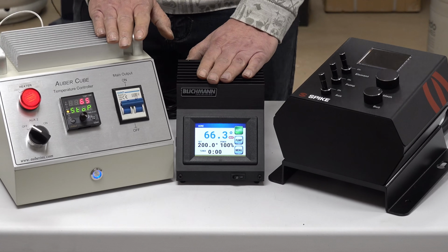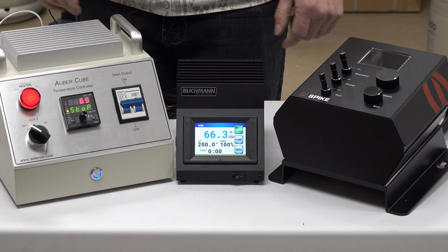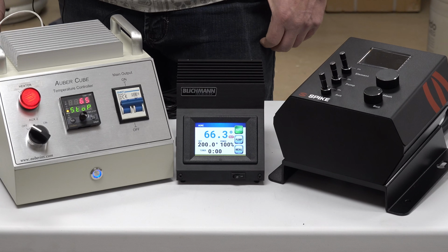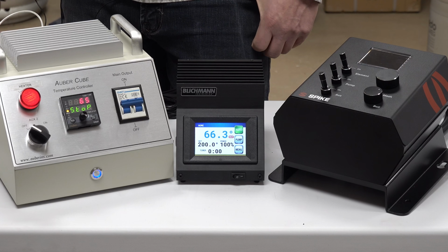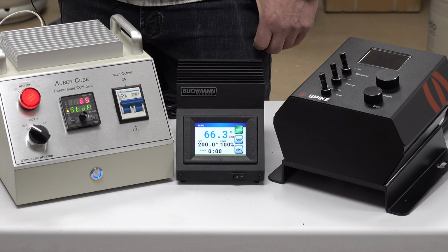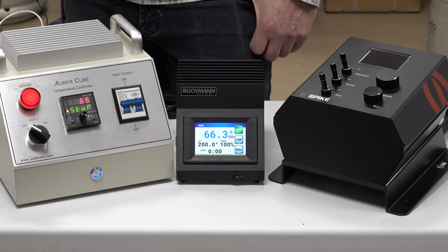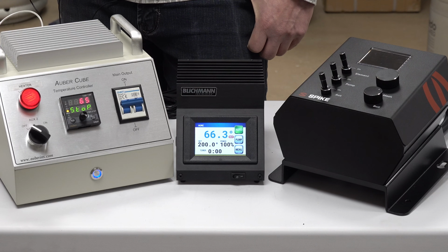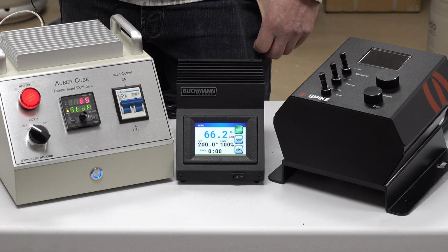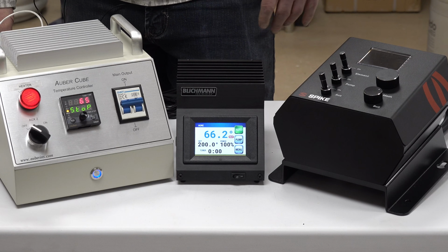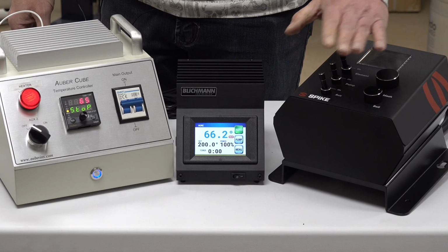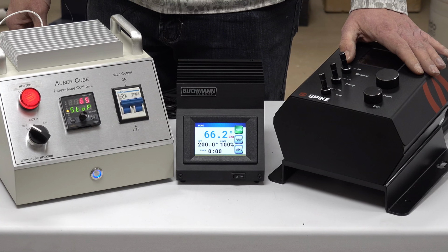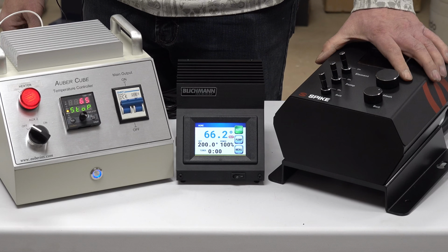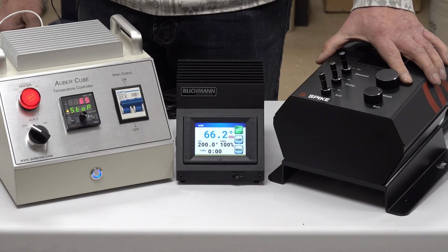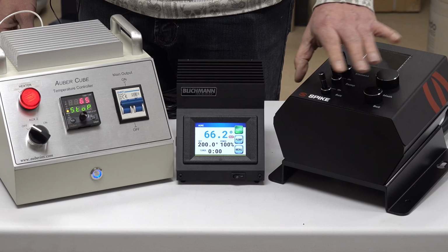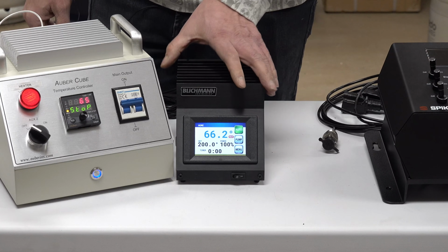Now the other thing to talk about, which gets a little complex, so we'll take this slowly, is multi-step temperature programming. I also like to call this the temperature-for-a-time style programming, such as 150 degrees Fahrenheit for 45 minutes, and so on. As we said, the Spike Solo is completely devoid of any scheduled programming — you just manually set a temperature and it holds on to that temperature indefinitely until you change it or turn the controller off. So multi-step timing is out for this one.